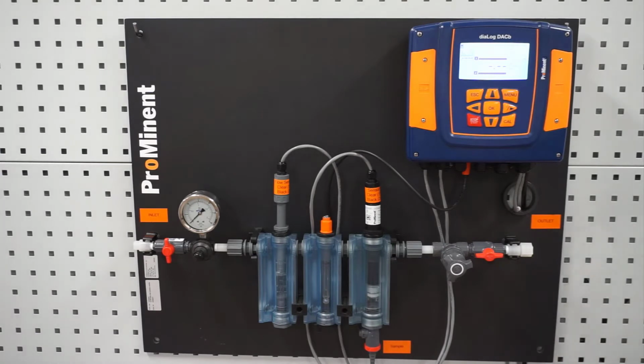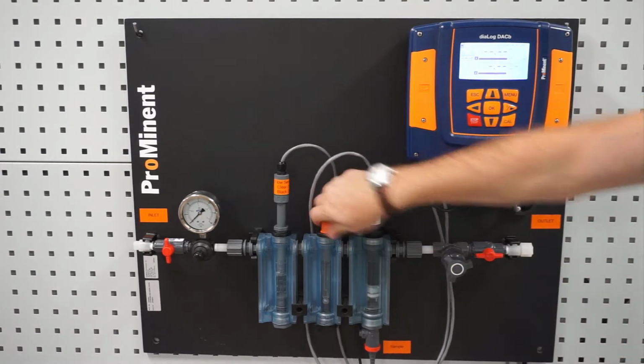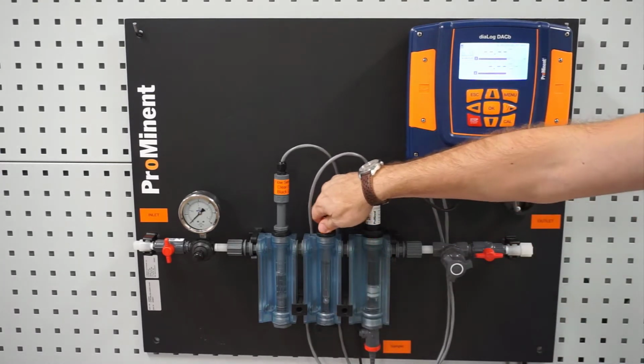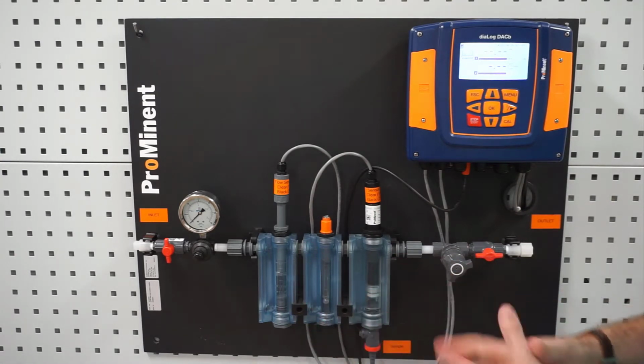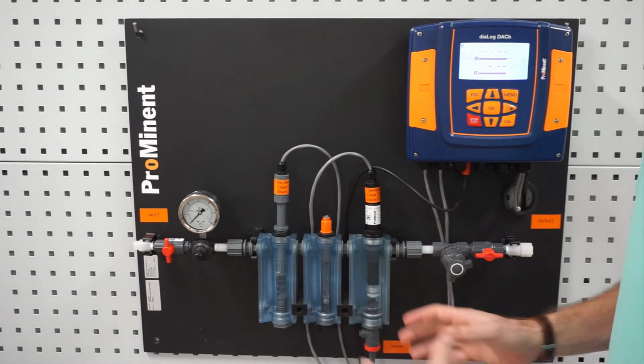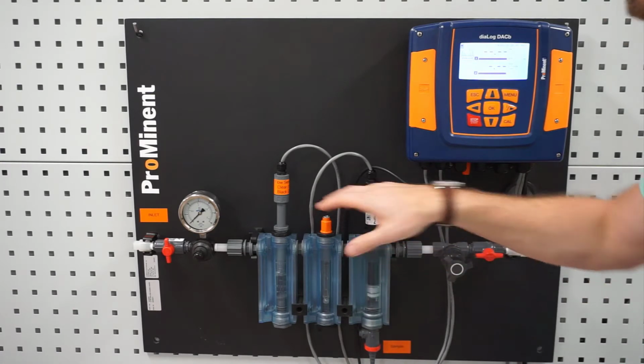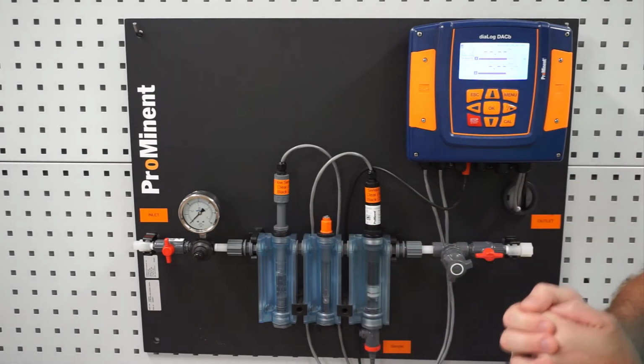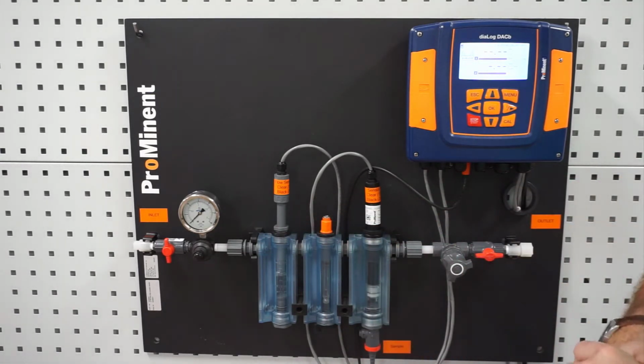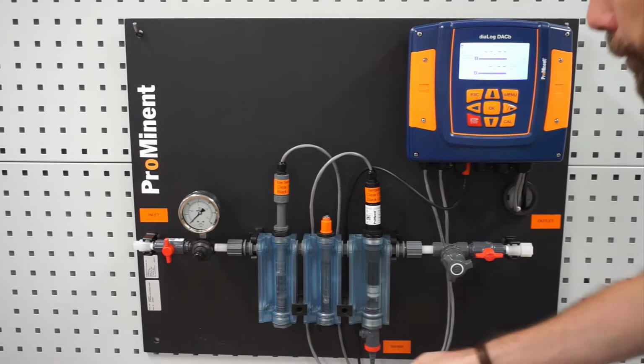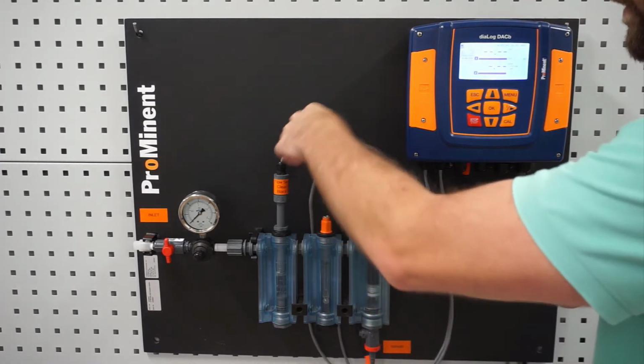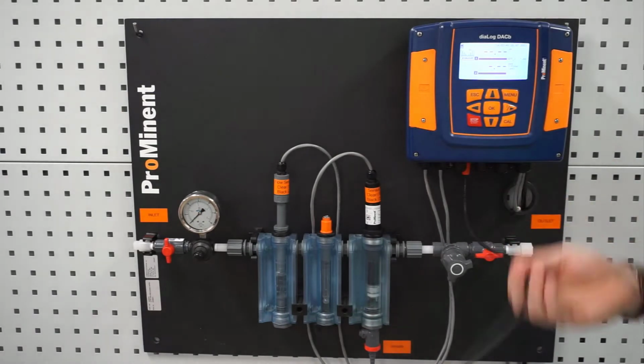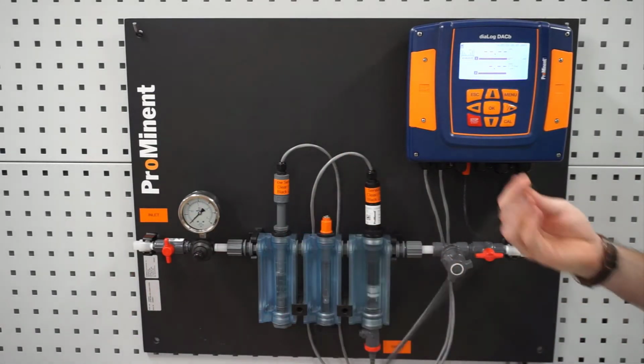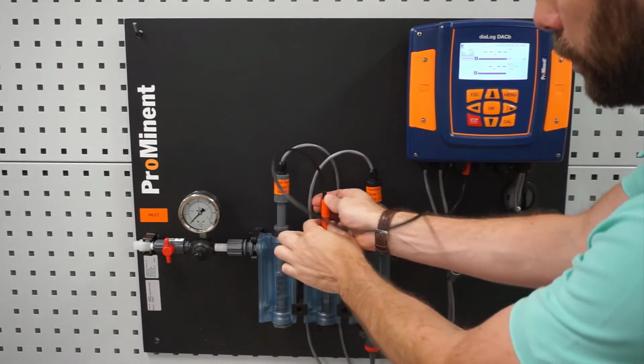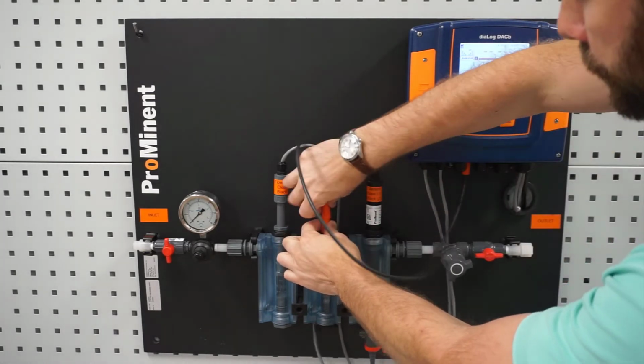You don't want to tighten that. You will risk the potential of cracking components here. Once we get this set up, we will have less than 15 psi of pressure in here. So we really don't need to crank down on our components because there's really not that much pressure in this flow cell. Once we get the sensor in there, we're going to find our pH sensor cable. It is a coax cable. It will screw onto the top.